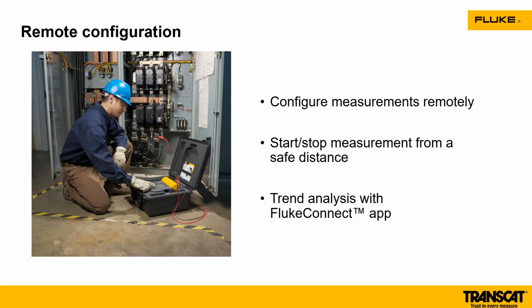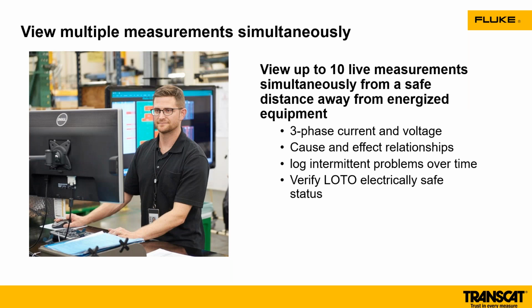Also, even now we have remote configurable tools, where you can remotely configure something like an insulation tester, getting in, configuring, doing high voltage insulation tests, but staying out of that boundary. So really that's the key win when we talk about a Bluetooth or a Wi-Fi device, keeping you out of that zone. With these devices, you can literally view up to 10 different measurements at one time. So if you're making voltage, current, whatever that may look like, three-phase voltage, three-phase current, you can easily hook these systems up and look at it from a distance. Really a win on that.